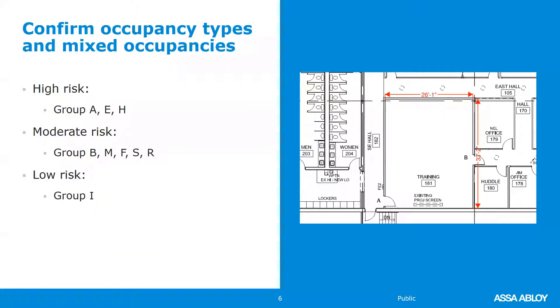You want to confirm the occupancy types and whether or not you have a mixed occupancy. The code is based on ordinary risk, moderate risk, and high risk. The high-risk occupancies are Group A Assembly, Group E Educational (K through 12 including nursery school), and Group H High Hazard. Those occupancies have more restrictions. Ordinary/moderate risk includes Group B Business, Group M Mercantile, Factory, Storage, and Residential occupancies.